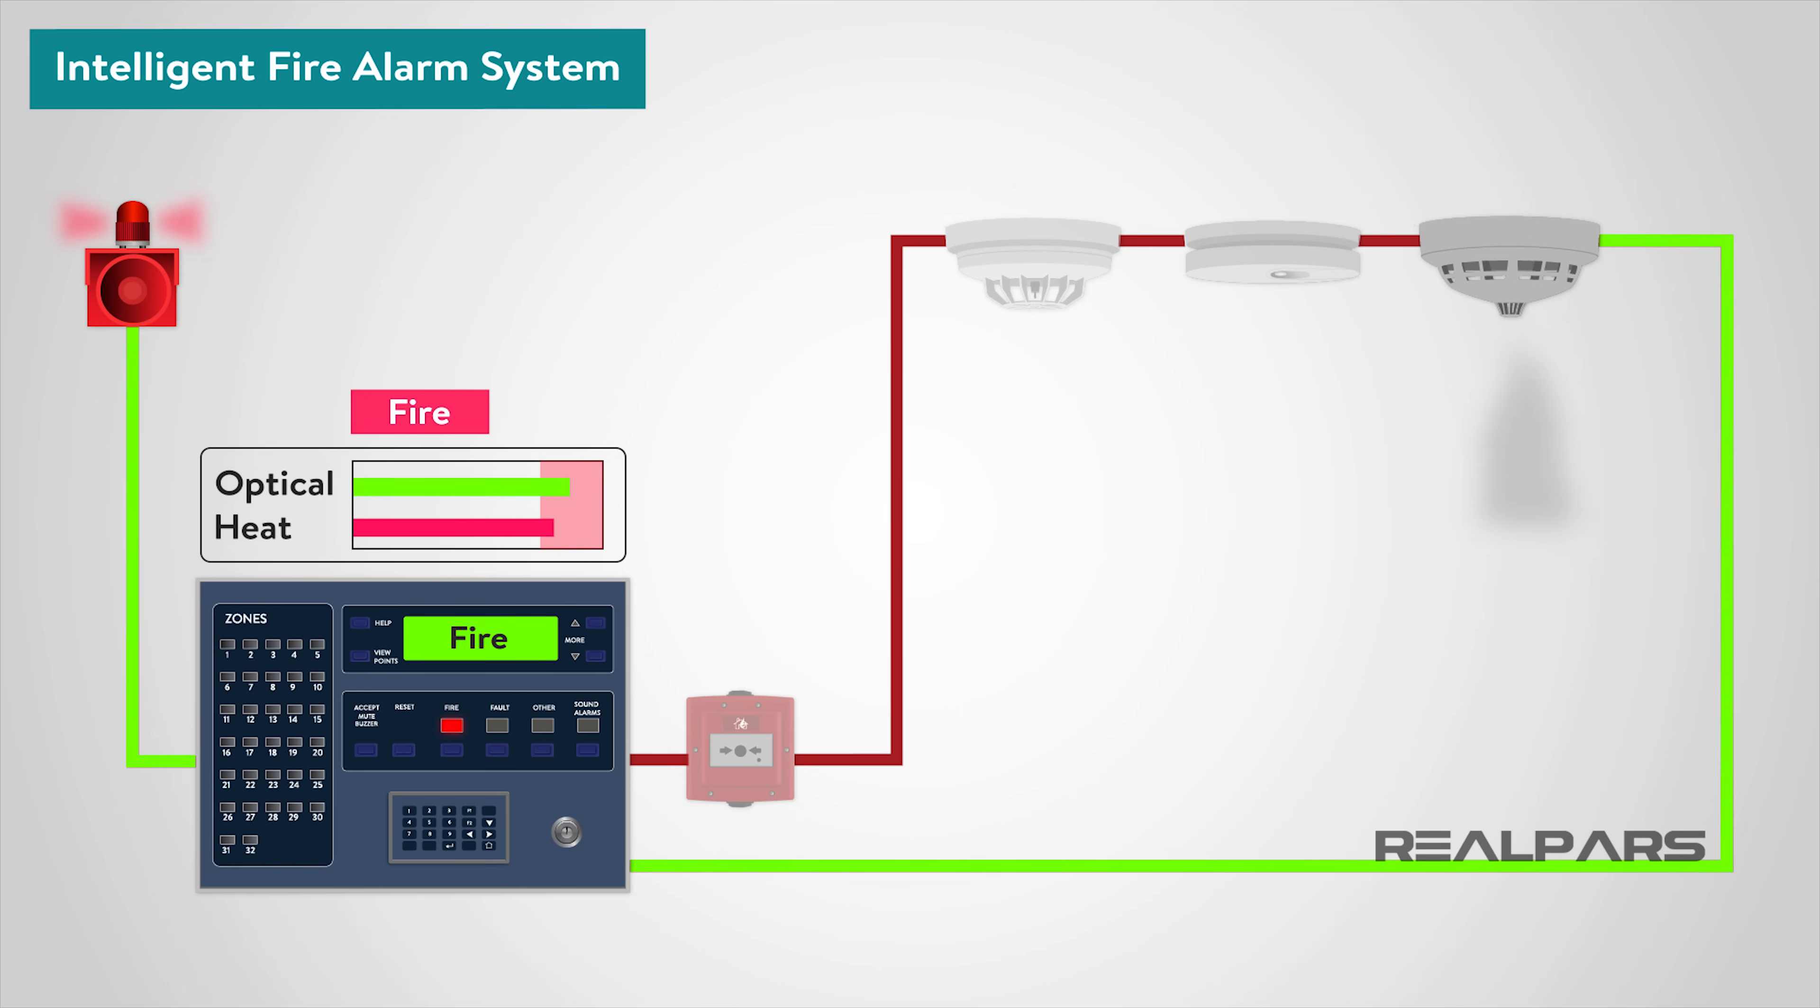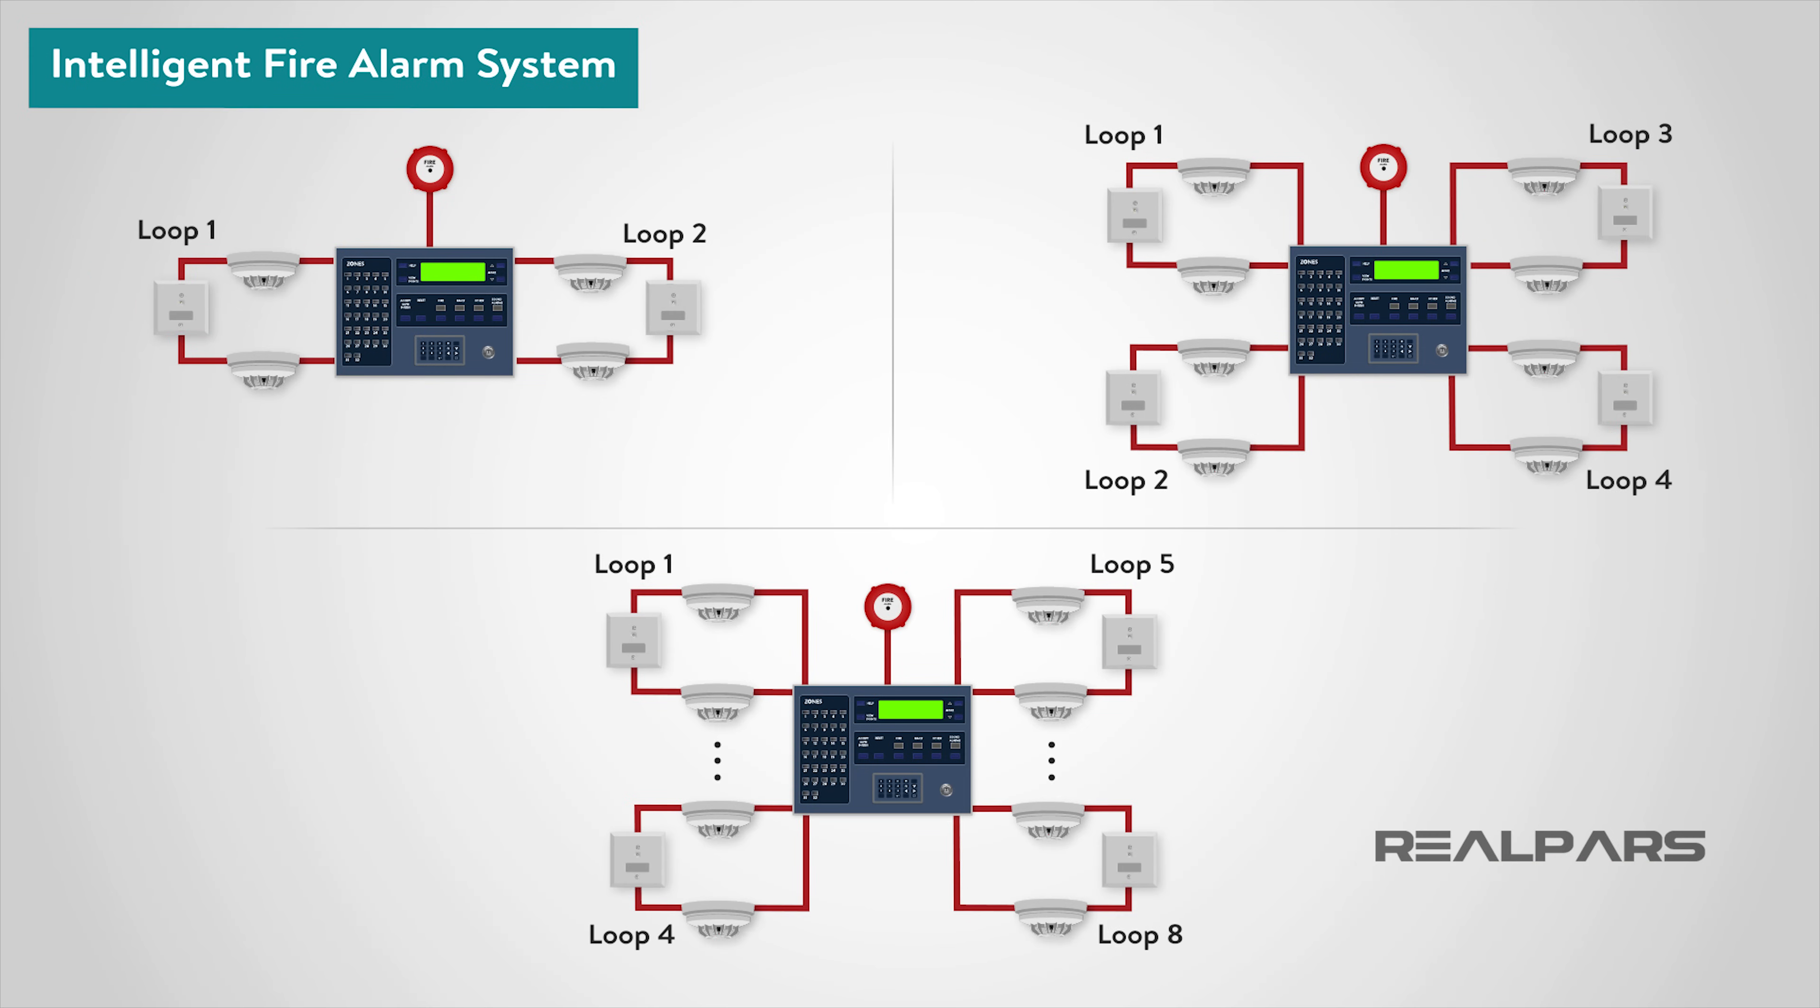Essentially, intelligent systems are far more complex, and incorporate far more facilities than conventional or addressable systems. Their primary purpose is to help prevent the occurrence of false alarms. Intelligent fire alarm systems are available in 2, 4, and 8 loop versions, which means large premises can be monitored from one single panel.